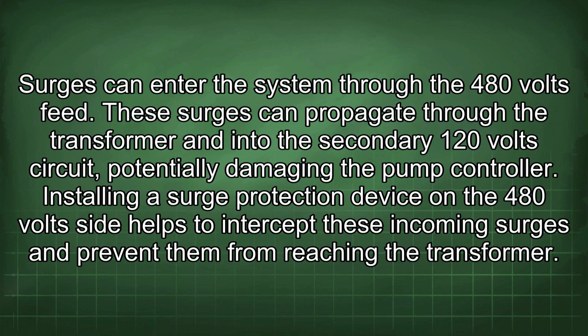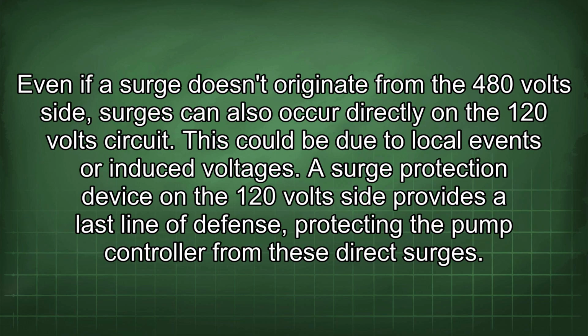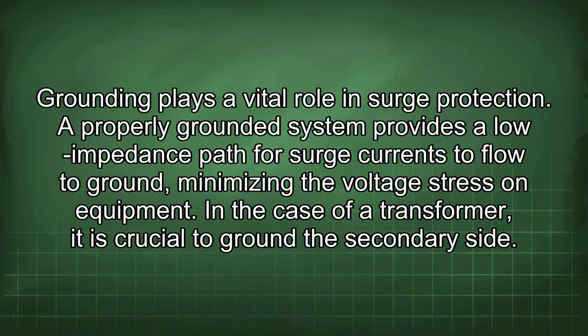Even if a surge doesn't originate from the 480 volt side, surges can also occur directly on the 120 volt circuit. This could be due to local events or induced voltages. A surge protection device on the 120 volt side provides a last line of defense, protecting the pump controller from these direct surges. Grounding plays a vital role in surge protection.